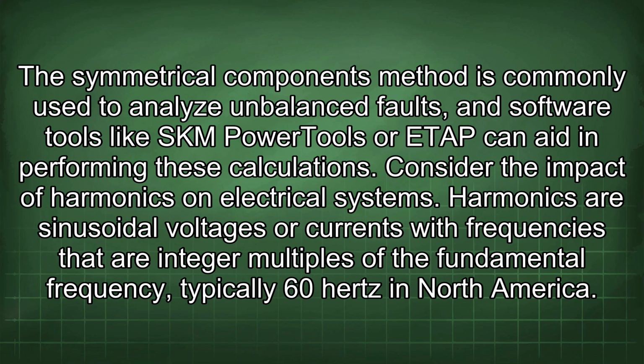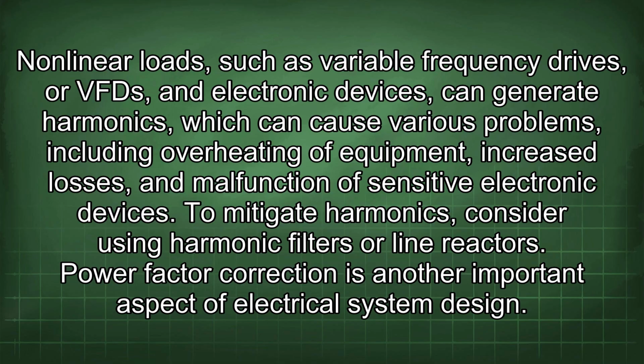Consider the impact of harmonics on electrical systems. Harmonics are sinusoidal voltages or currents with frequencies that are integer multiples of the fundamental frequency, typically 60 Hz in North America. Nonlinear loads such as variable frequency drives, or VFDs, and electronic devices can generate harmonics, which can cause various problems, including overheating of equipment, increased losses, and malfunction of sensitive electronic devices. To mitigate harmonics, consider using harmonic filters or line reactors.